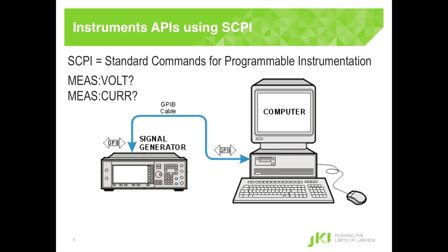And that API to the instrument is what made that instrument valuable in the context of a larger system. Maybe it's a rack of these instruments with some software that integrates them all into a test system that has subsystems, which are boxed instruments. And it allows the automation of the testing so that you don't have a manual tester pushing buttons, rewiring things, pushing more buttons.